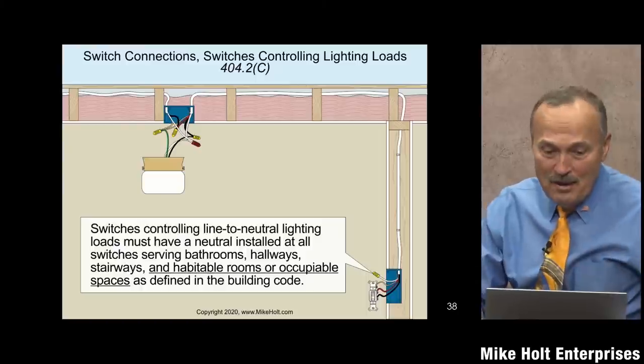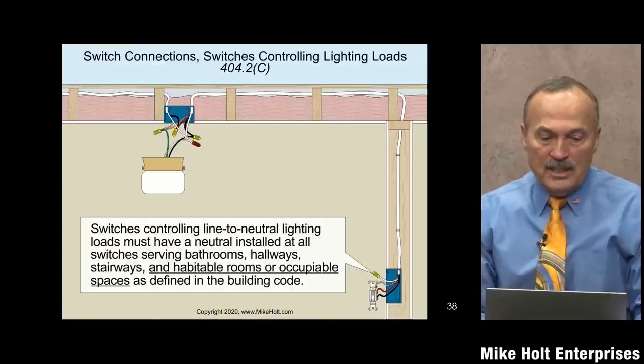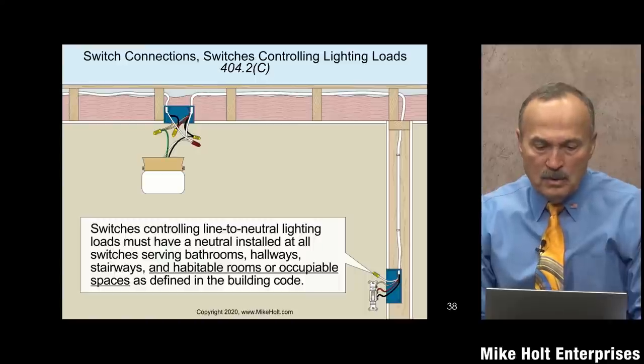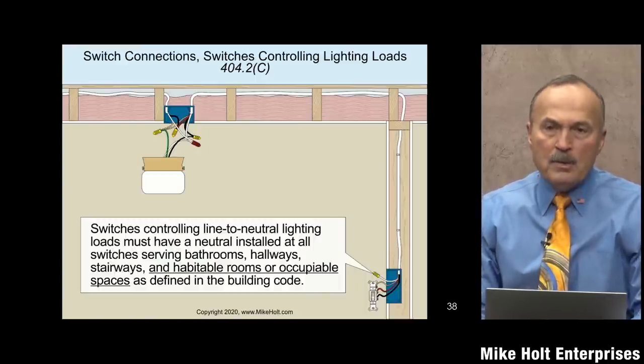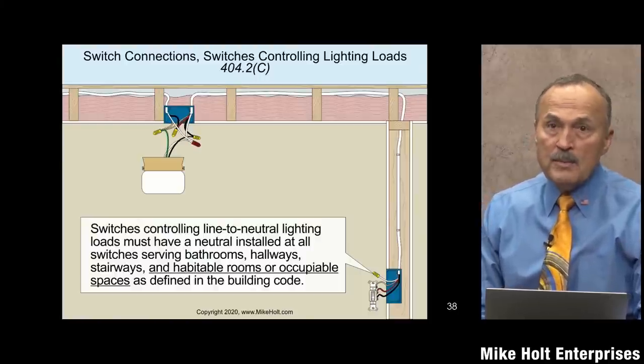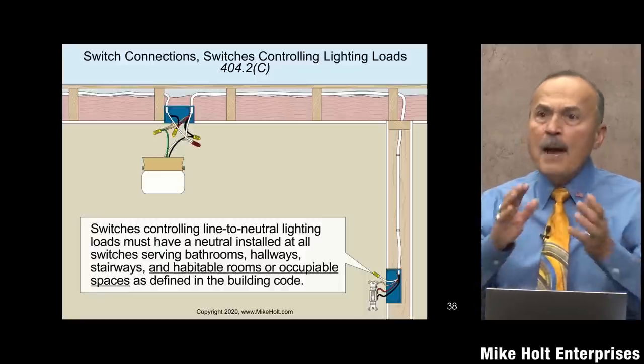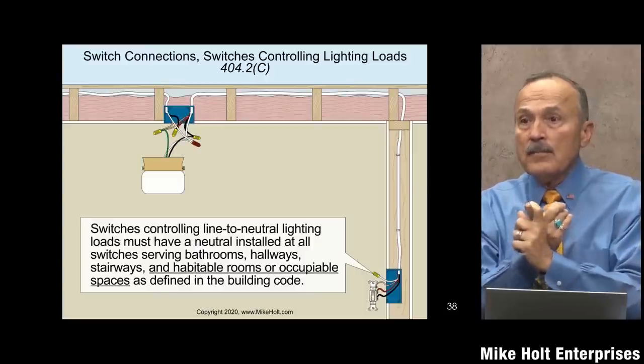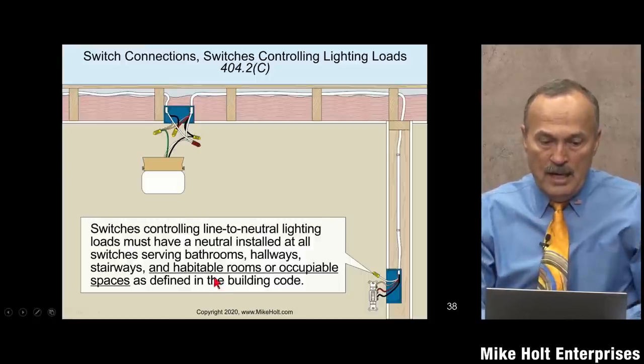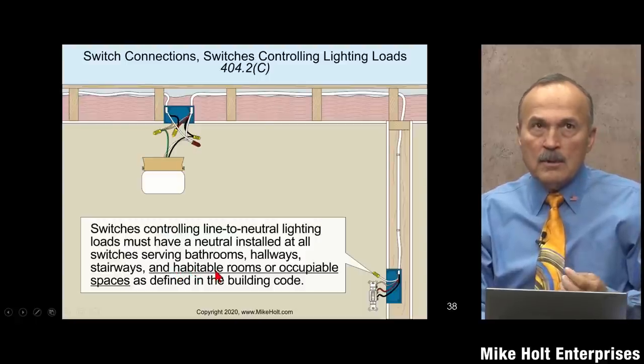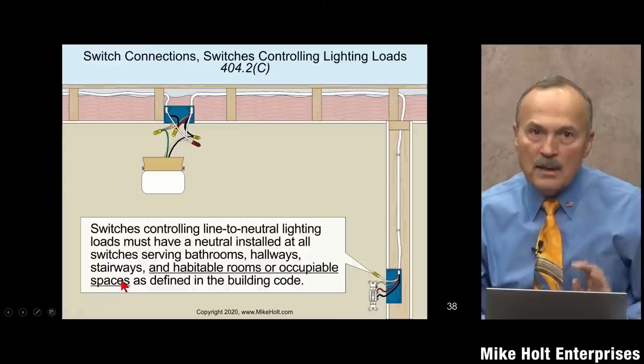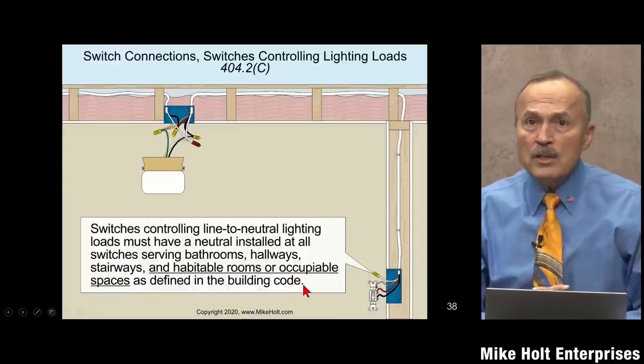Section 404.2C — switches controlling line-to-neutral lighting loads must have a neutral installed. All switches serving bathrooms, hallways, stairways, habitable rooms — which includes sleeping, living, eating, kitchen and cooking areas — and dining rooms must have a neutral at the switch location.